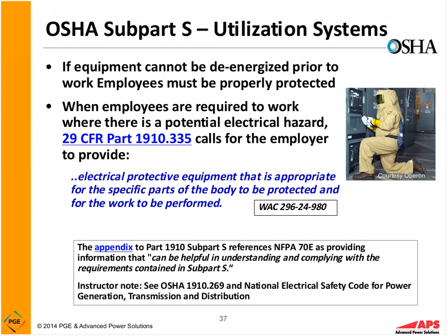So OSHA also says if equipment cannot be de-energized prior to work, employees must be properly protected. So when employees are required to work where there's a potential electrical hazard, 1910.335 calls for the employer to provide electrical protective equipment that's appropriate for the specific parts of the body to be protected and the work to be performed. You say, well, they're not telling me specifically what to do. You're right, they're not. But OSHA Subpart S references NFPA 70E, the standard for electrical safety, which says it can provide information that can be helpful in understanding and complying with these requirements.